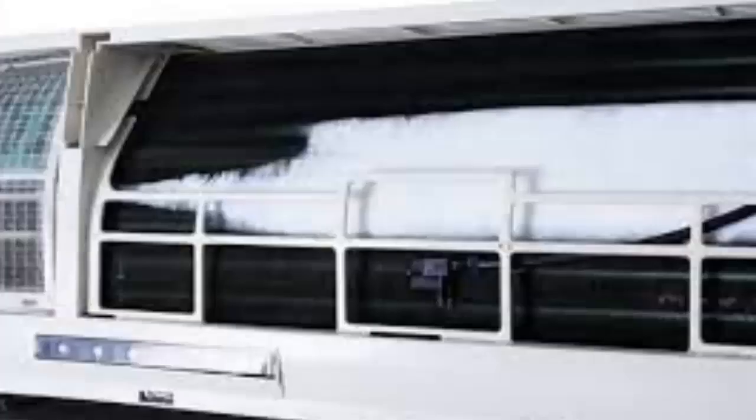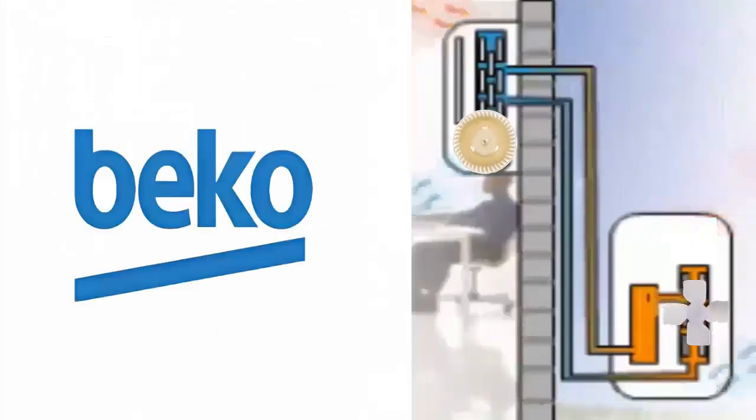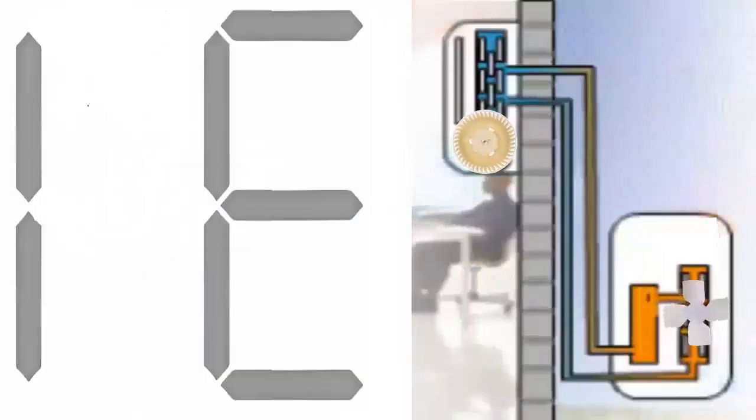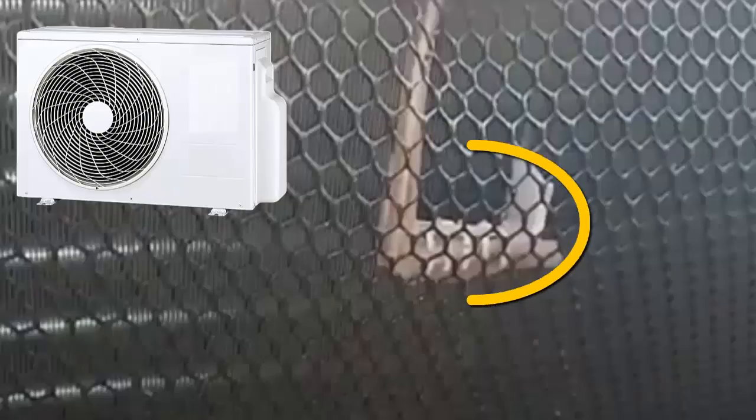Error code 1E refers to issues with the sensor located in the outdoor unit, which measures the air temperature drawn in by the outdoor unit's fan, allowing an average temperature reading of the outdoor environment.